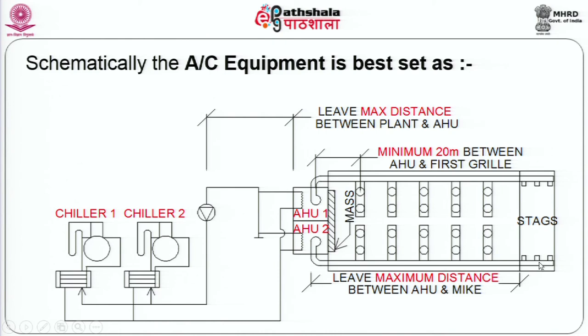I think with this it has highlighted these factors. If one lines these rooms properly, if one lines the systems of ducting properly and uses the kind of diffusers that I have shown here, so that you have air diffusion parallel to the ceiling, the vane noise is far less when it travels to the mic, and one would have a system which is par excellence.